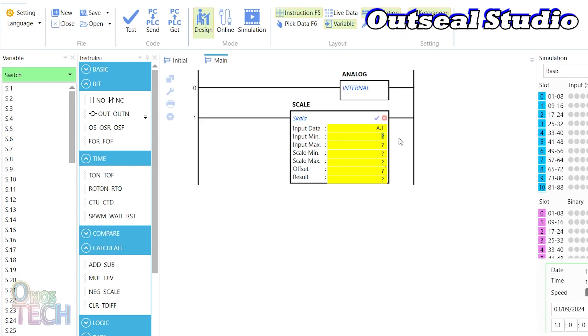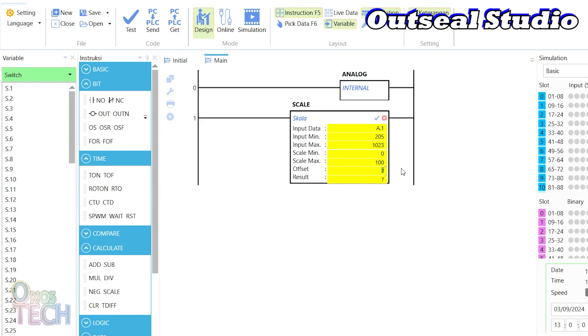Therefore, the input min should be 205, the input max 1023, the scaled min 0, the scaled max 100, offset 0, and the result sent to I.1.